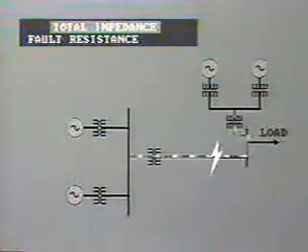The total impedance is made up of: A, resistance of the fault itself; B, resistance and reactance, that is, impedance of the line conductors; C, impedance of any transformers or reactors in the circuit; and D, impedance of the generating source. The calculation of probable fault currents for different conditions is a very important task for the system designer.